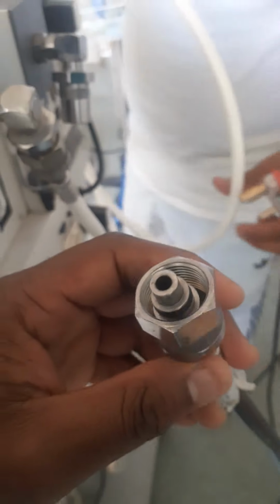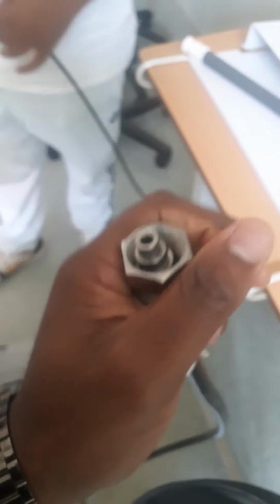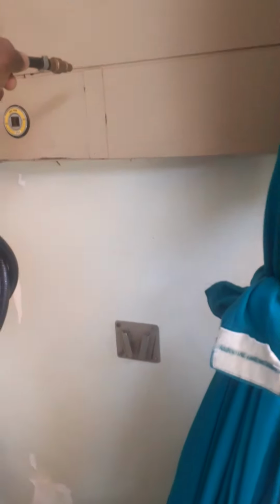So remember to always disconnect this, because the reason we connected this was that we don't have the oxygen supply this side. But after testing, you must remove it. They must not use this air, because this medical air is for backup. Then you can connect this. This one goes here, and then this one will go to the wall, to the supply, if there was one.